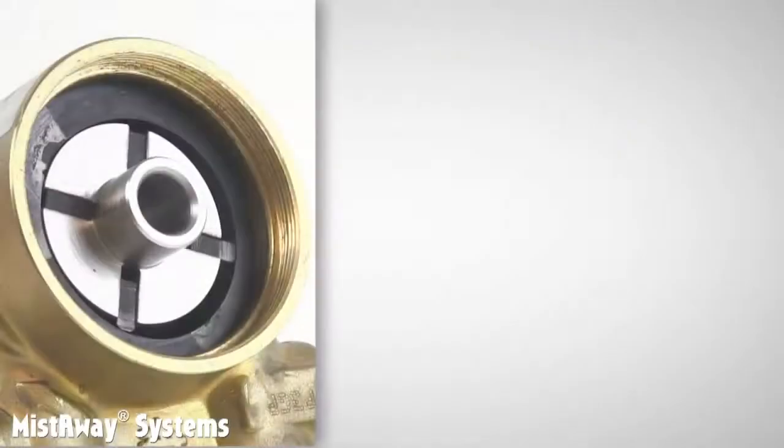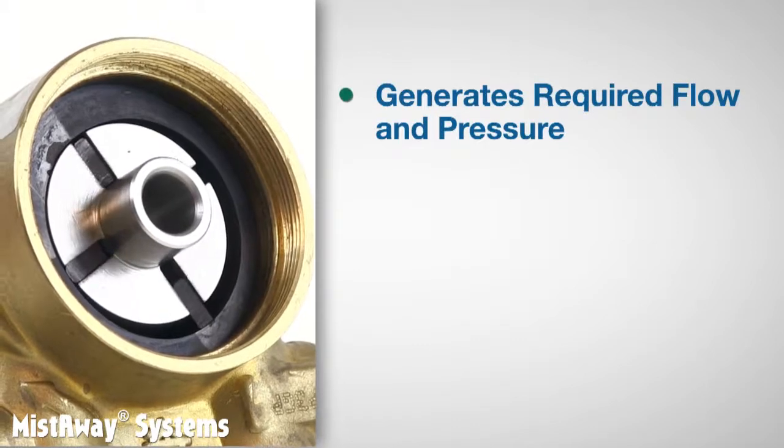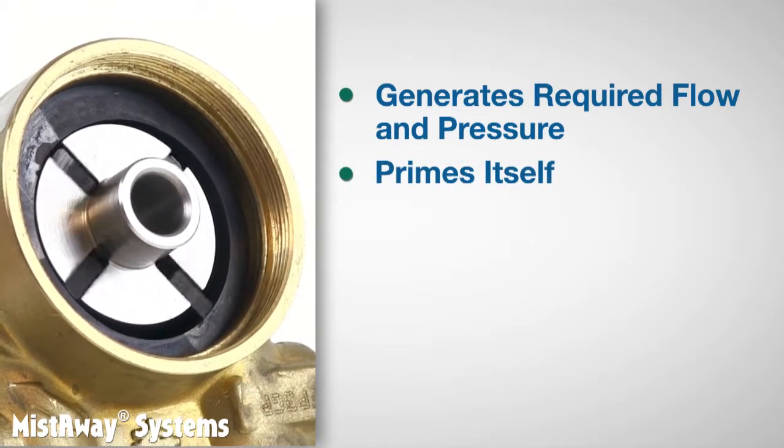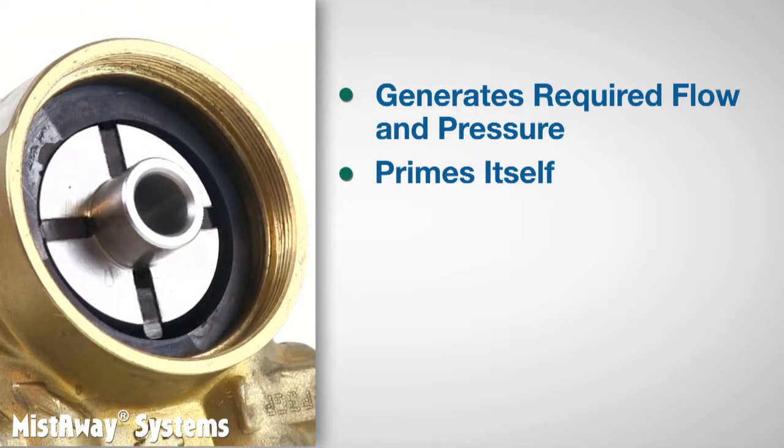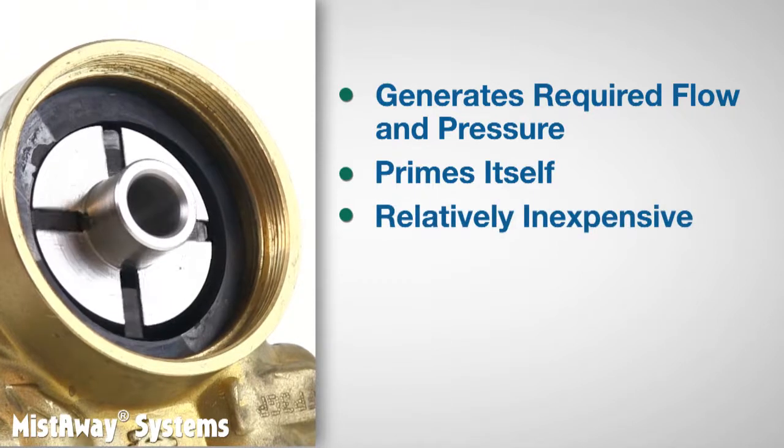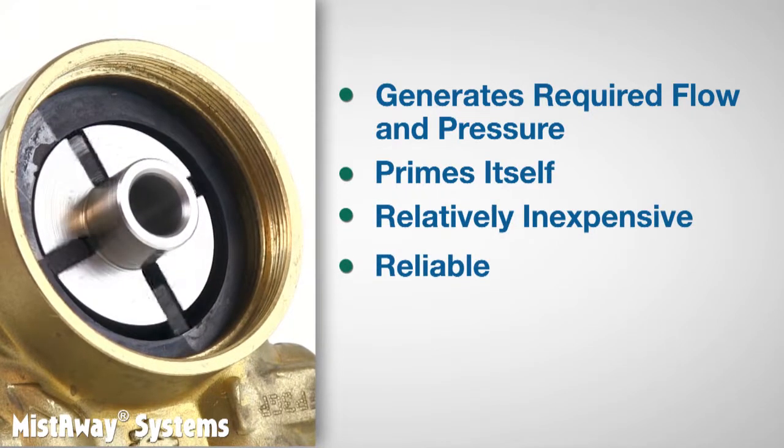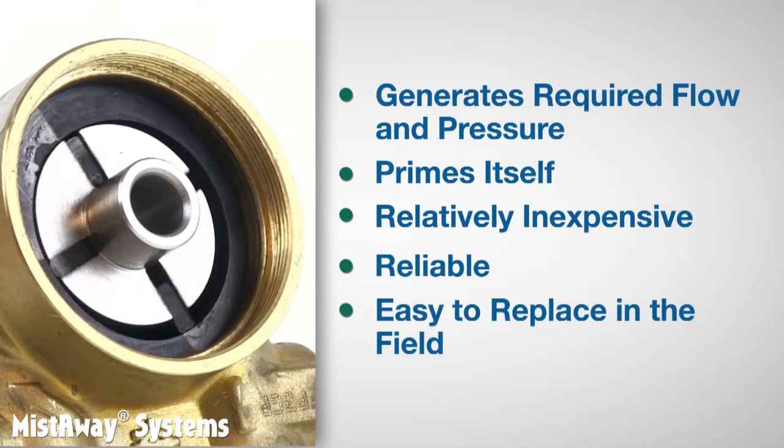There are a number of reasons we use this type of pump in our systems. It generates the flow and pressure that our systems require. It will prime itself, meaning that the pump doesn't have to be full of fluid to start, like some other kinds of pumps. It is relatively inexpensive. It is very reliable, provided the intake filter is routinely cleaned. And finally, it is easy to replace in the field if it does fail.